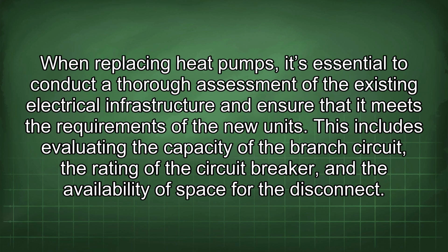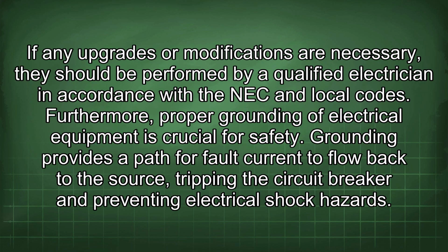When replacing heat pumps, it's essential to conduct a thorough assessment of the existing electrical infrastructure and ensure that it meets the requirements of the new units. This includes evaluating the capacity of the branch circuit, the rating of the circuit breaker, and the availability of space for the disconnect. If any upgrades or modifications are necessary, they should be performed by a qualified electrician in accordance with the NEC and local codes.